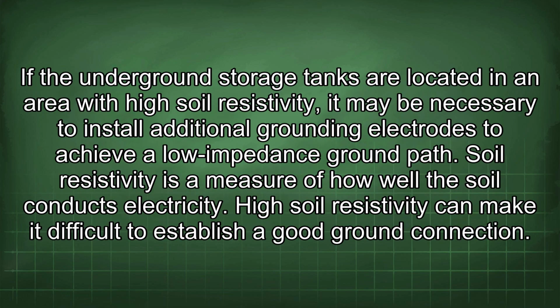If the underground storage tanks are located in an area with high soil resistivity, it may be necessary to install additional grounding electrodes to achieve a low impedance ground path. Soil resistivity is a measure of how well the soil conducts electricity. High soil resistivity can make it difficult to establish a good ground connection.